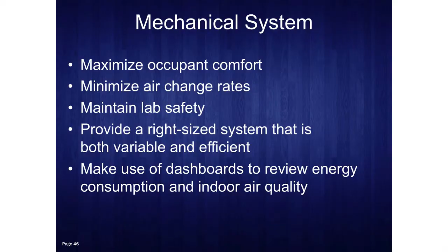So, mechanical system. Again, just like lighting, we want it to be dynamic. Give people the ability to have a dynamic system that responds based on what they're doing in their space, whether they're there or not, whether they're doing something intensive with the fume hood in use or not. Maintain that level of safety, it's key, it has to happen. If not, what we really want to do is talk about augmenting the level of safety in these laboratories. Right size the equipment. Systems are so oversized most of the time, and if they're oversized, chances are you're losing out on the savings that's there.